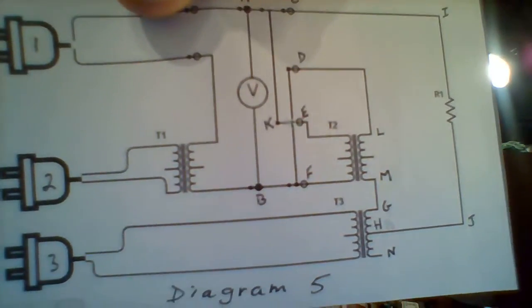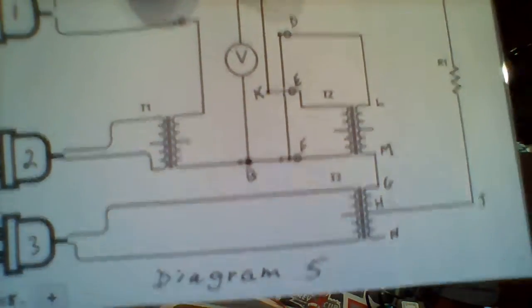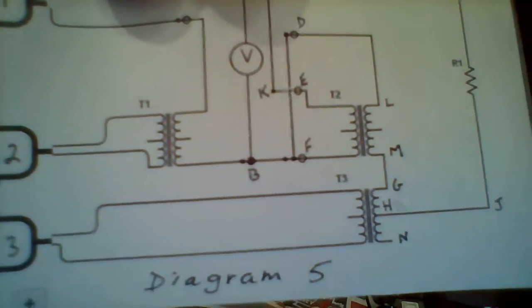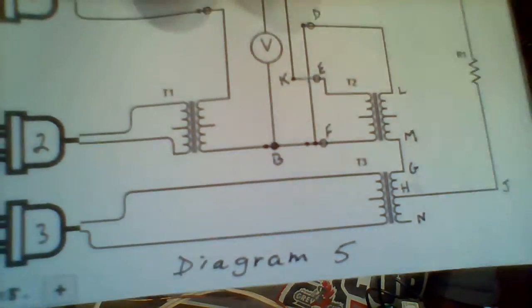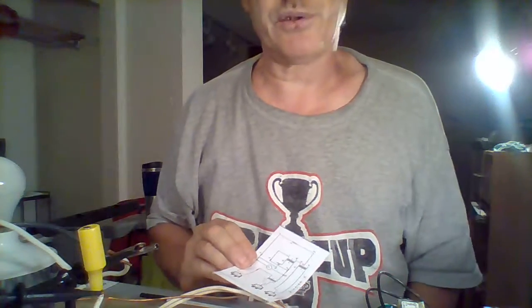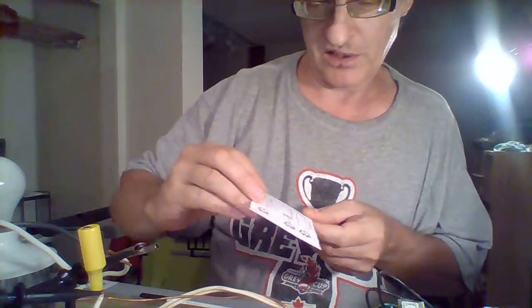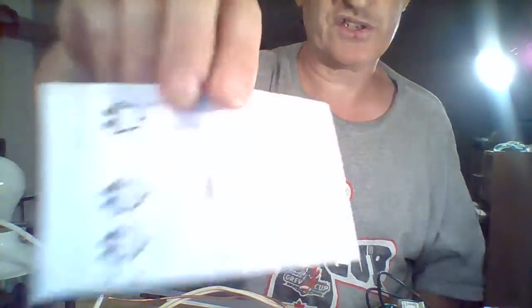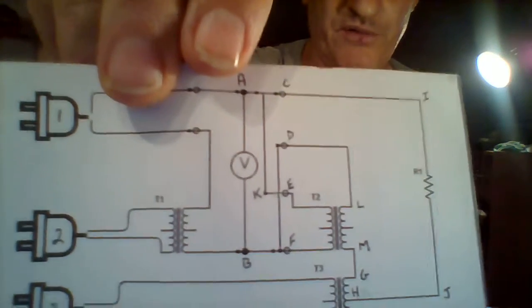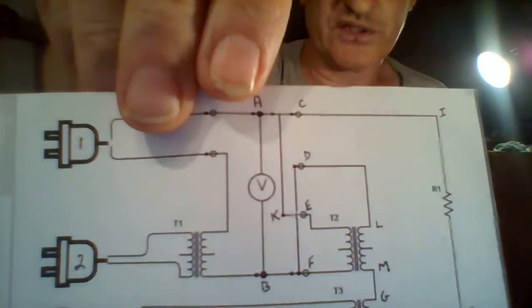Well, first you create the 480 volts, and then you wire that up in series through the connection M and G. That's a series connection. But that center tap should be an adjustable tap that you can slide up and down, and you adjust that for 67 volts. Therefore, 480 volts plus 67 volts equals 547 volts.